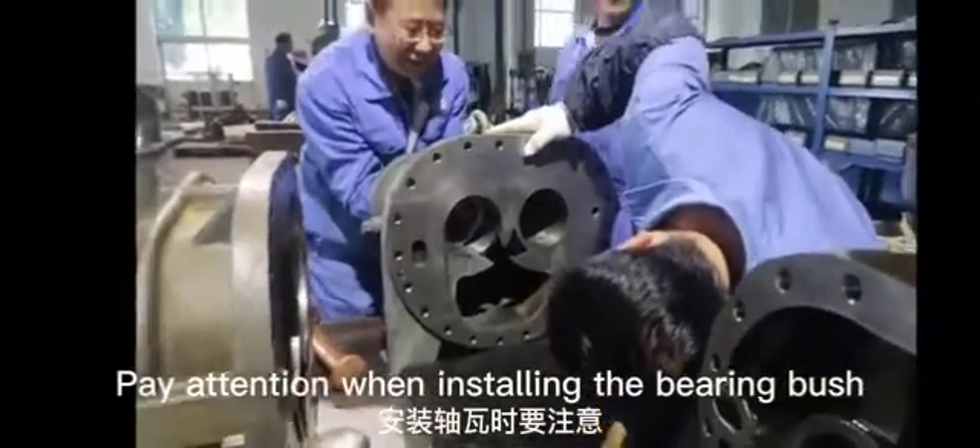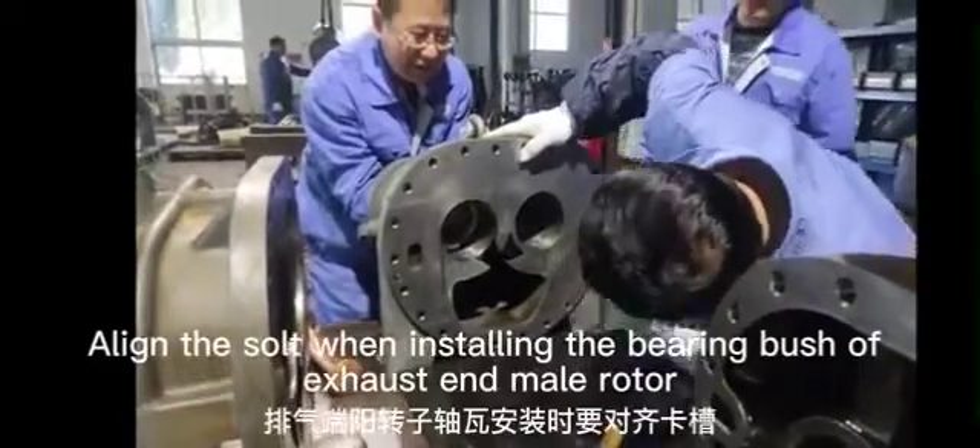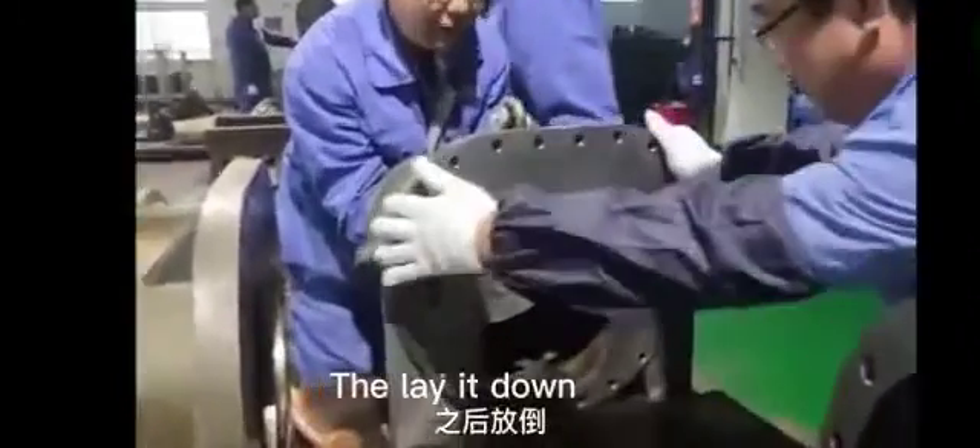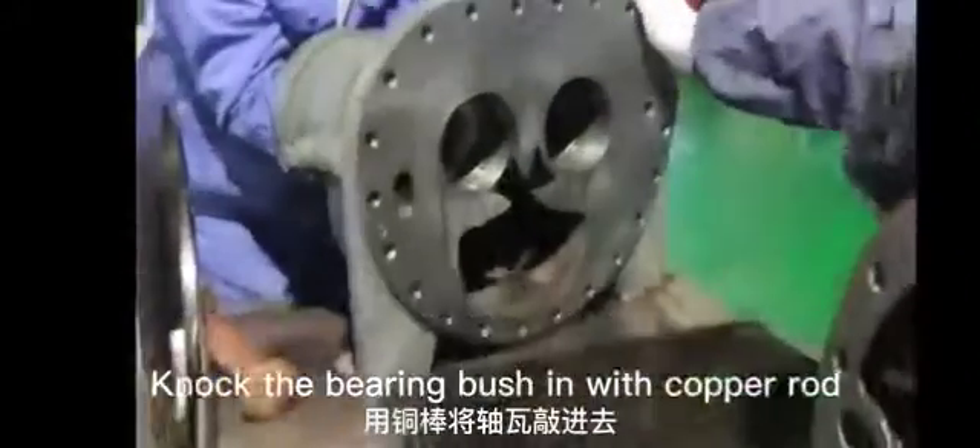Pay attention when installing the bearing bush — specifically the bearing bush of the exhaust end male rotor. Lay it down and knock the bearing bush in with a copper rod.